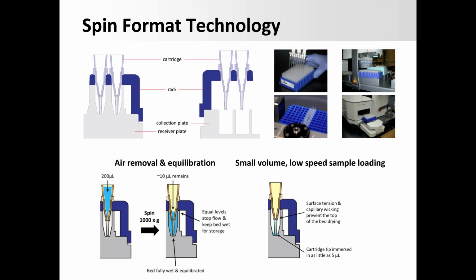Now, the other way you can get air into the bed is by drying. The bed only has a 5 microliter volume, so it's got maybe 3 or 4 microliters total of liquid in it, and it's very easy for it to dry out and again get what is, for this bed, a substantial air bubble. So with the receiver plate, because the bottom of the cartridge is suspended just above the bottom of the receiver plate, as soon as you have as little as 5 microliters of liquid through the cartridge, the tip of the cartridge is immersed in liquid. That prevents the tip from drying out, and capillary action prevents the top of the bed from drying out. So we can now spin liquid through the bed without any danger of it drying out whatsoever.